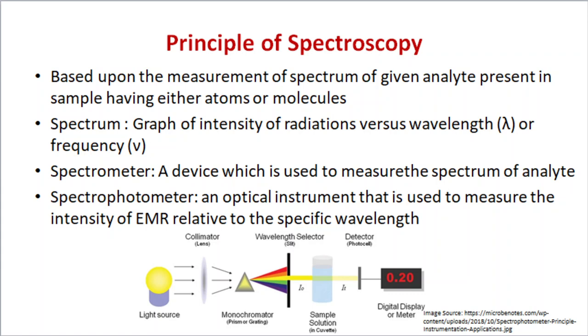In a spectrophotometer, the sample must be in solution form, and the solvent containing the analyte must be optically transparent in the specific wavelength region. Light from the light source passes through a collimator lens, then a monochromator — a prism or grating — where it is split into multiple wavelengths. A wavelength selector (slit) selects the desired wavelength, which then enters the sample solution in the cuvette. Finally, a photocell detector and digital display meter show the absorbance, emission, or transmittance.